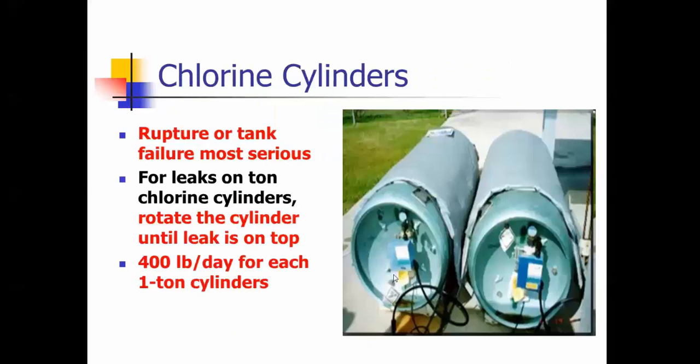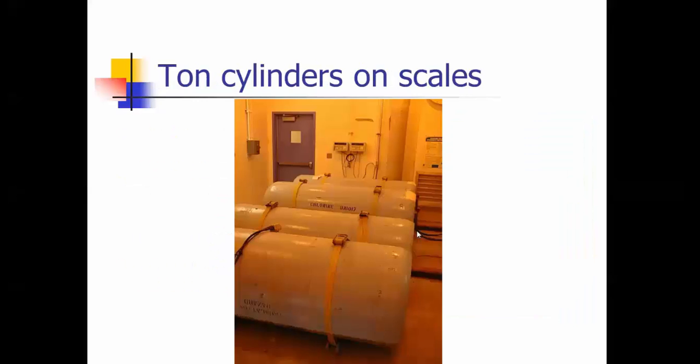The maximum feed rate is 400 pounds per day on a ton cylinder. Here's some ton cylinders. They need to be strapped down, and they're on scales.